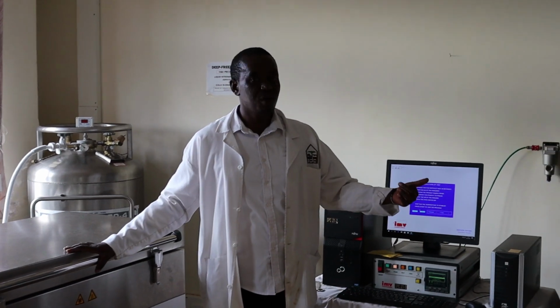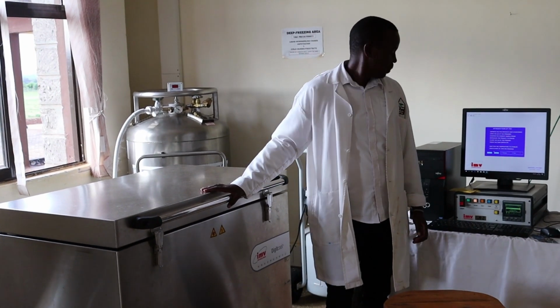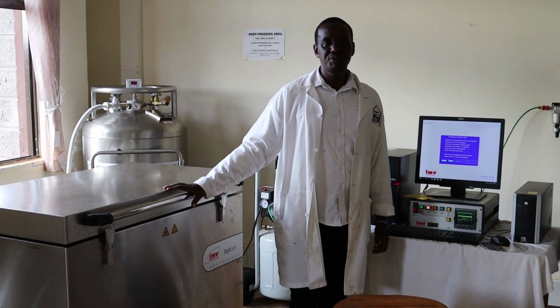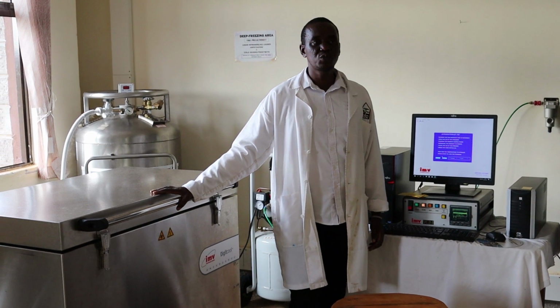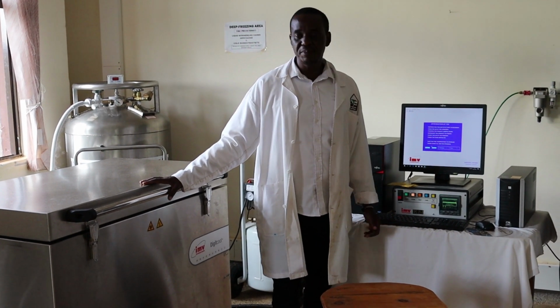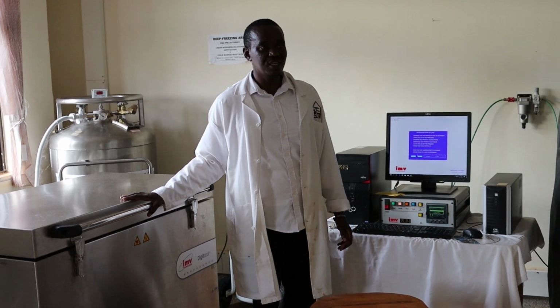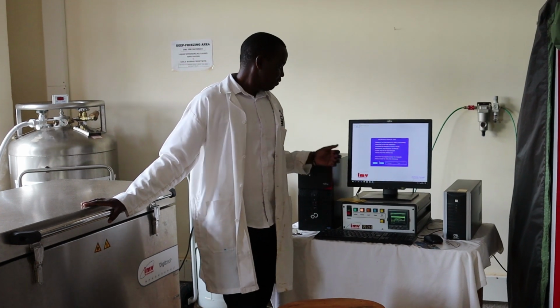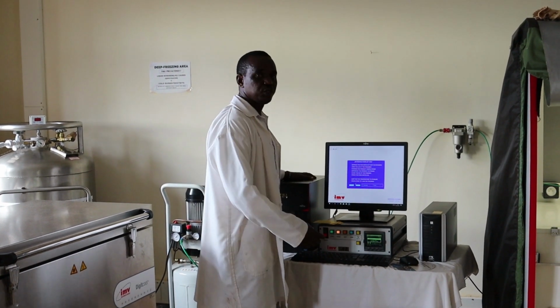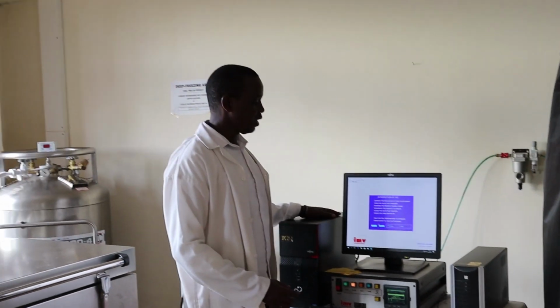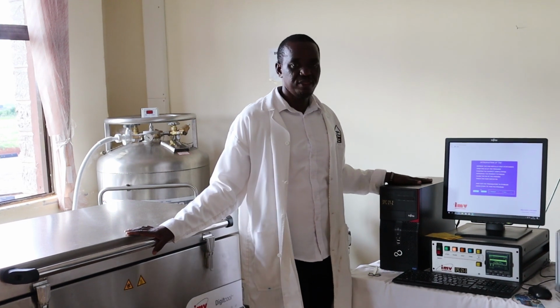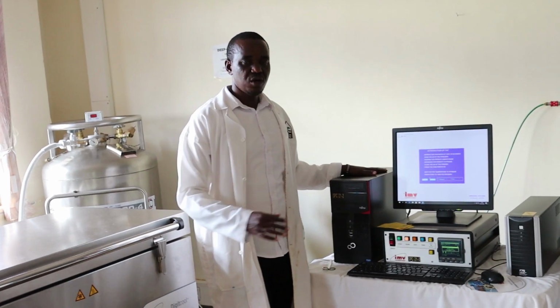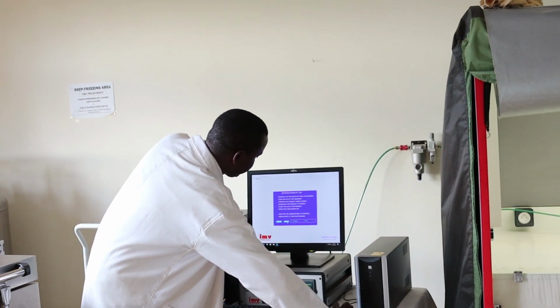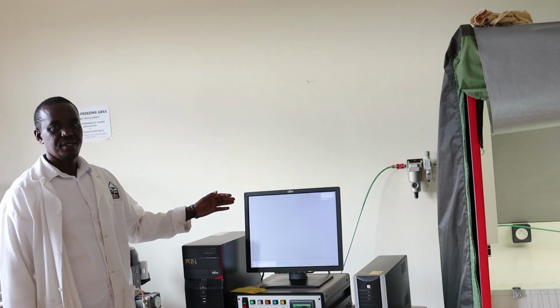Okay, get started. So we have just loaded the semen that we were filling into the freezing chamber. Now we are waiting for the temperature to stabilize because the freezing process has to start at 4 degrees centigrade. So we are waiting for the chamber temperature to stabilize at 4 degrees so that we can start off the program. If it's not ready, it will not start because the entire system is computerized. This freezing container is actually controlled by this computer here. So it's a whole computerized program. So we'll try to start. Because it's ready, we have started. The temperature is already stabilized at 4 degrees.